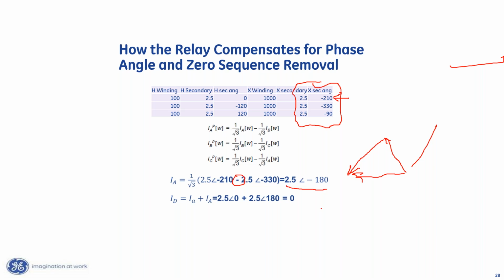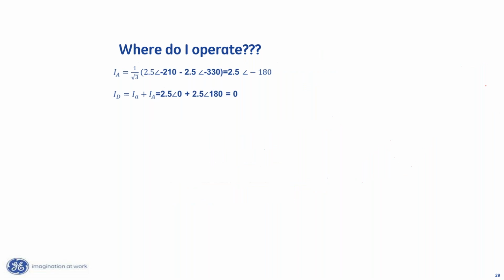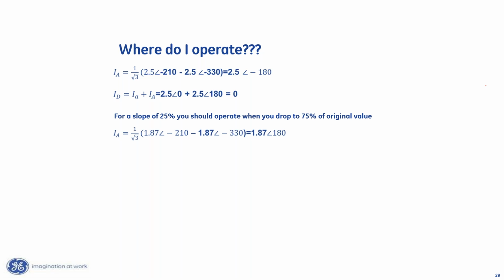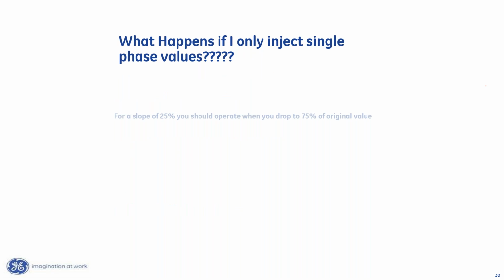So then when I do my differential calculation and take my H winding current, that's 2.5 at 0 degrees, plus that 2.5 at 180 degrees, those vectorially sum to 0. If I wanted to figure out where I would operate, if I got this 0 differential point, and my slope's 25%, I'd operate when I dropped to 75% of my original value. Okay.